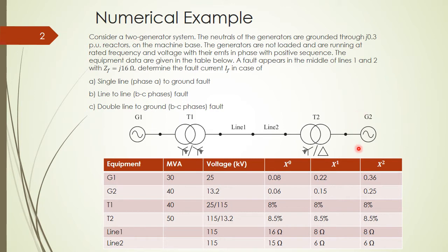We consider a two-generator system, and the generators are connecting with each other via two transformers T1 and T2. T1 is a Y-to-Y connection with the neutral connected to ground. T2 is a Y-to-Delta connection with the neutral on the primary side connecting to the ground. T1 and T2 are connecting to each other via two lines, line 1 and line 2. The neutral of generator 1 and generator 2 are also connected to ground via a 0.3 PU reactor.